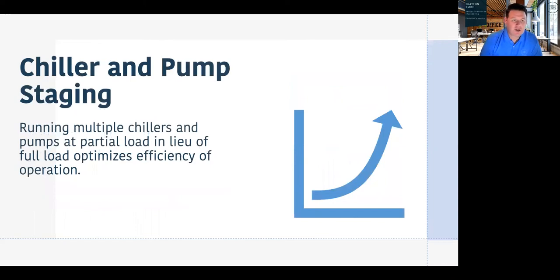Next slide, please. Chiller and pump staging. We talk a lot about running multiple chillers and pumps at part load as opposed to maxing out load on a single piece of equipment, optimizing our equipment by running it in that sweet spot in the power curve, and understanding where that lives for each individual piece of equipment.